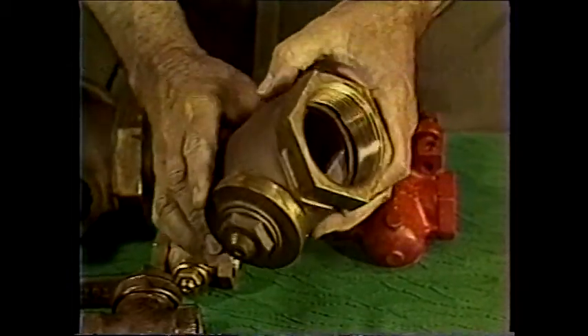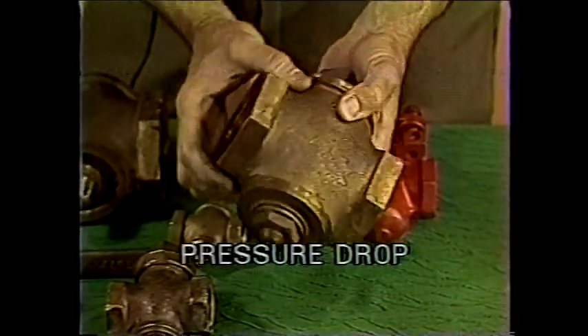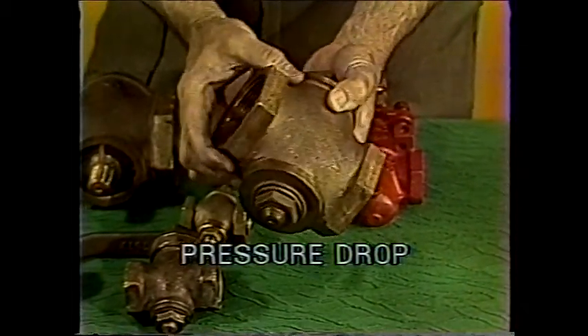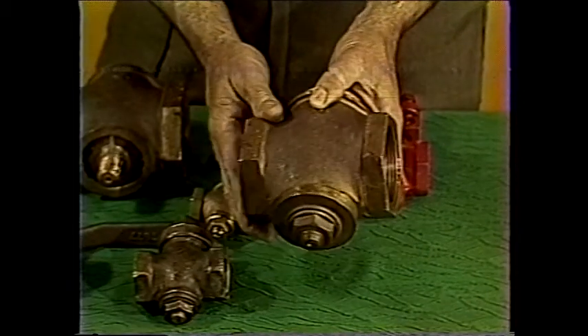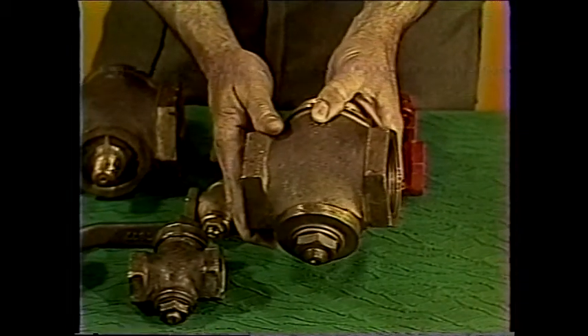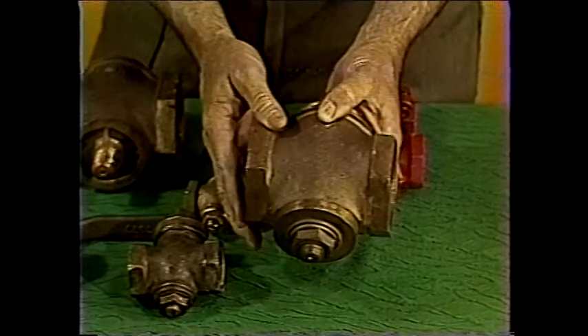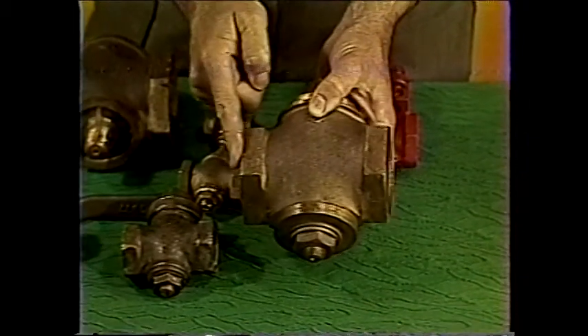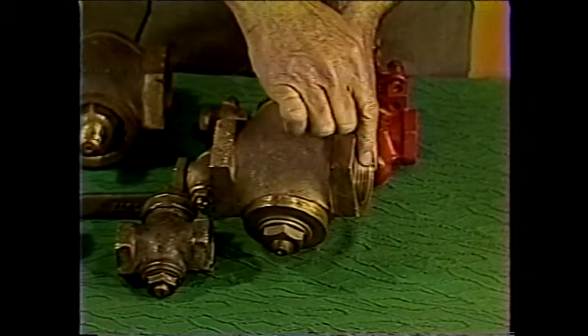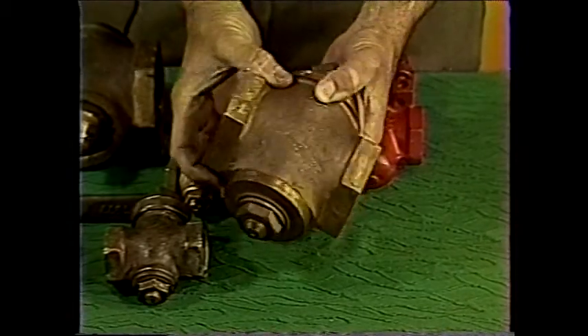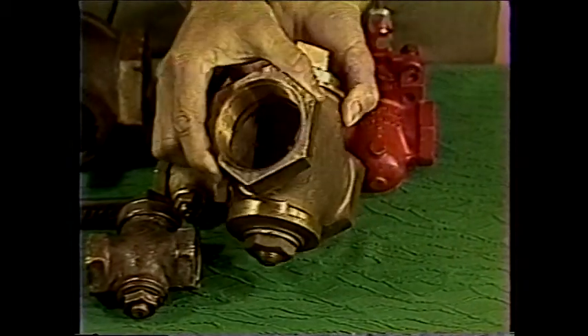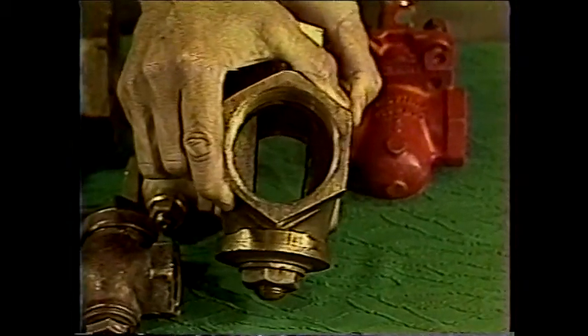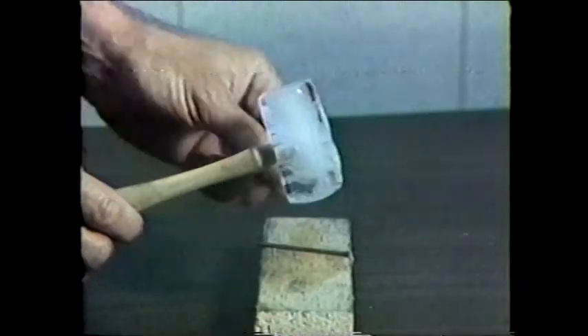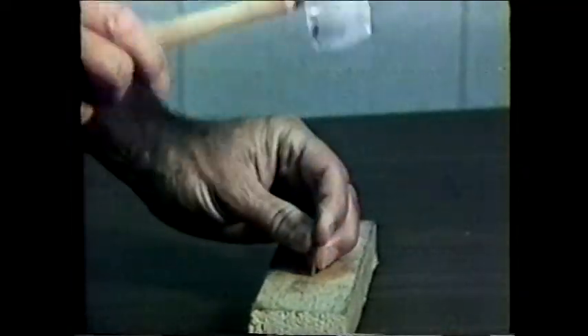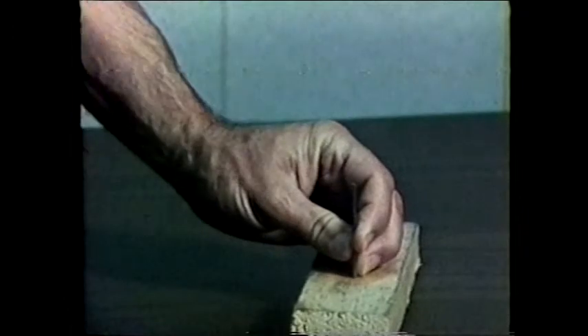Pressure drop is a term to remember, since it's commonly used when referring to a valve's operation. It is the loss in pressure between any 2 points in a system. In this case, between the inlet here and the outlet here. It is a result of the friction between the material being handled and the valve which it comes in contact with. While we're covering common terms in the valve field, another term to discuss is water hammer.